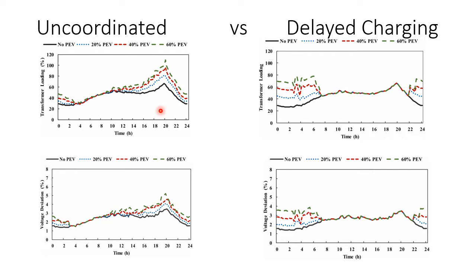If everyone charges whenever they want, although it says whenever they want, they're most probably charging right after they come back home, they relax for a little bit and plug in. Then the peak demand gets pretty high and exceeds the 100% rating of the transformer, and that's not good for the utility because that's going to reduce the lifetime of the transformer. So at 60% it's not good. But if people delay their charging time till at least 2200 hours, then that peak is gone, and even at 60% we are within 80% of transformer rating.